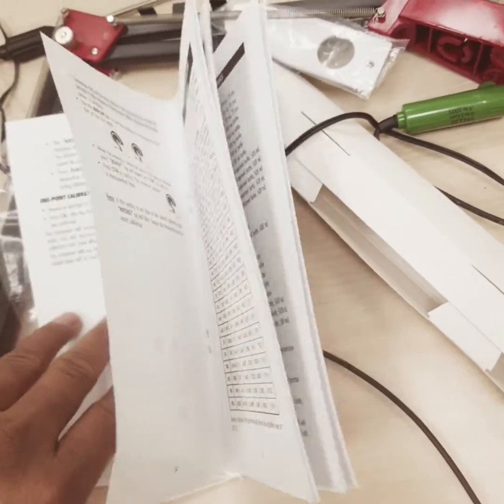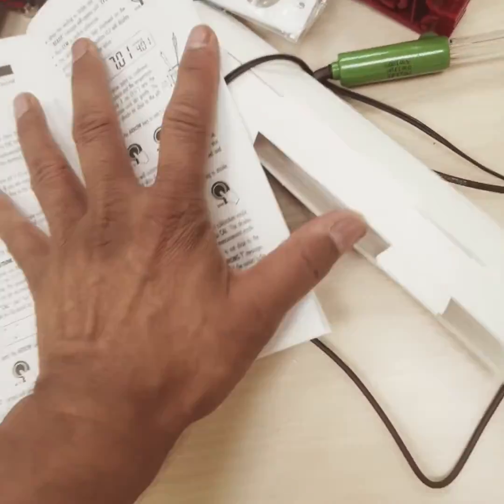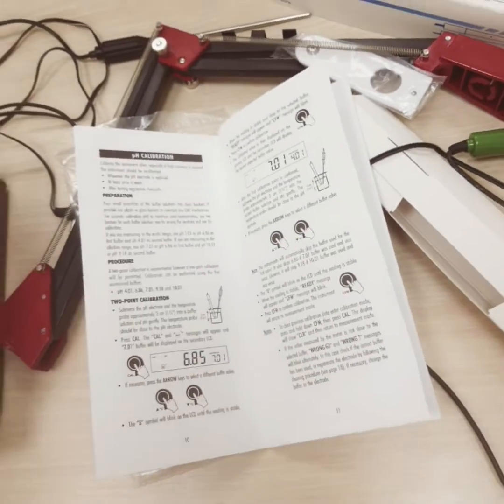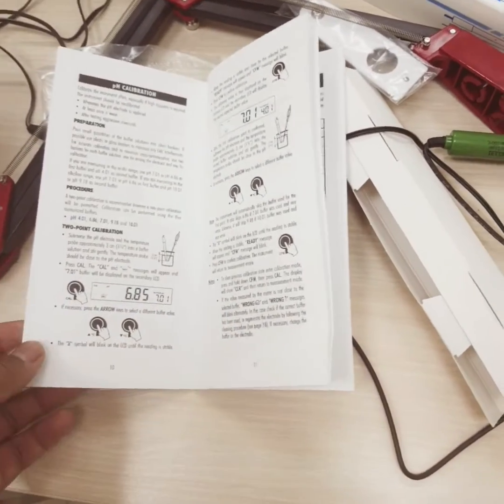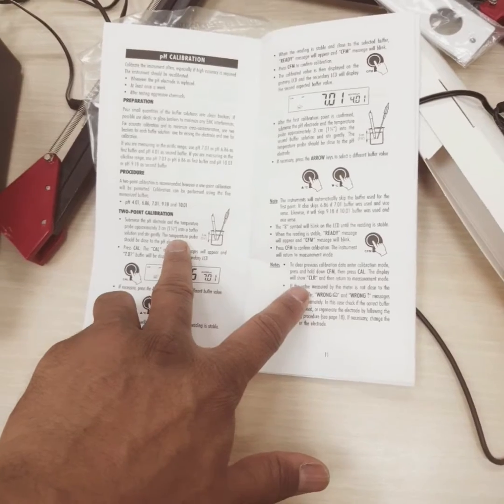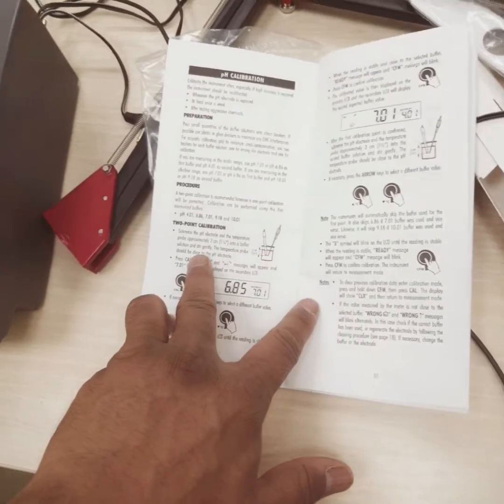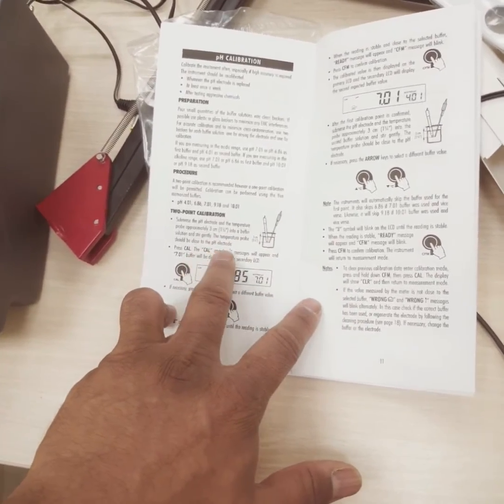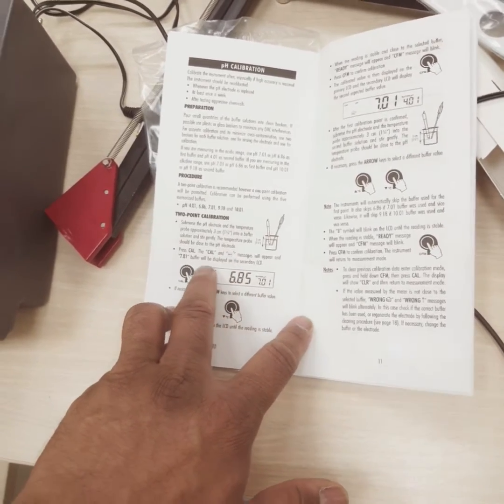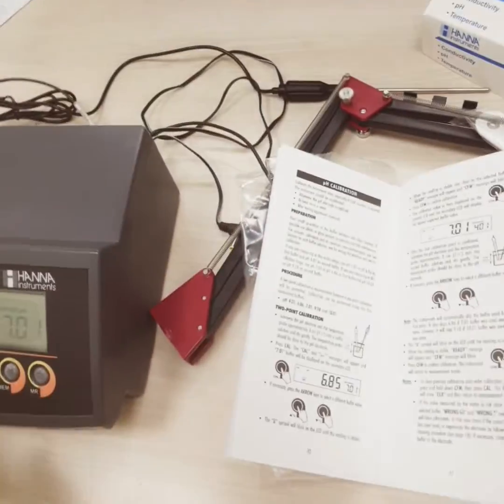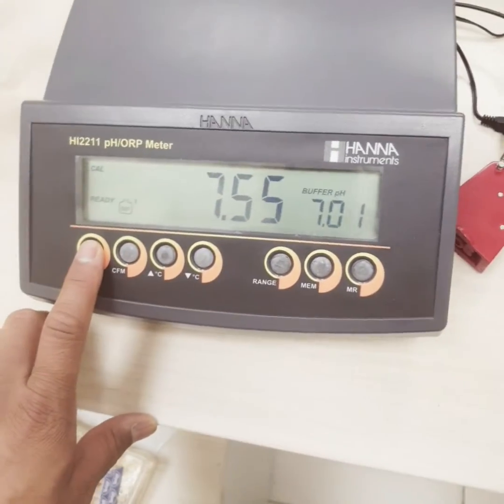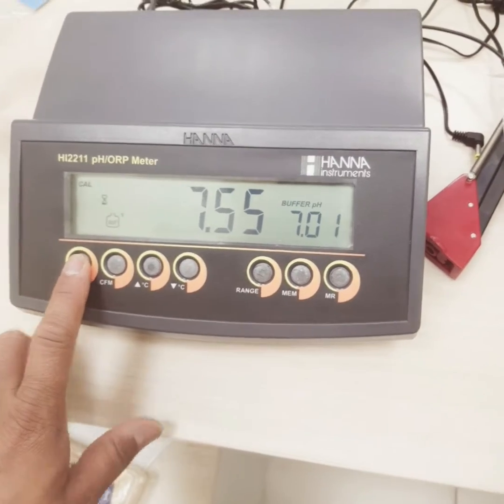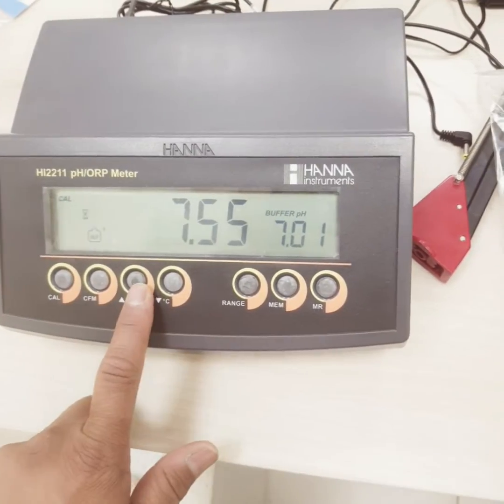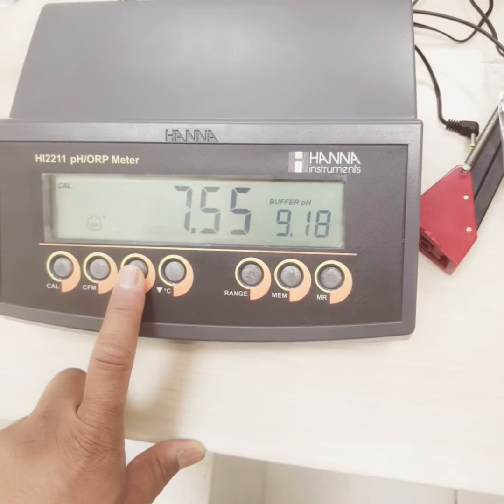So before starting the calibration part, you have to refer to the manual. The procedure says submerge the electrode and temperature probe approximately 1 1/4 inch or 3 centimeters into buffer solution and stir gently. The temperature probe should be close to the pH electrode. Okay, so we have now buffers. We'll try to transfer this to the vials. Okay, already I have started, so I have pressed cal. When you press cal, this window appears, and with these arrows you can change the buffers.